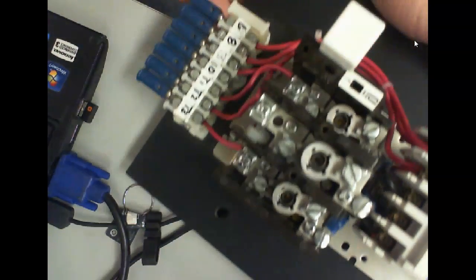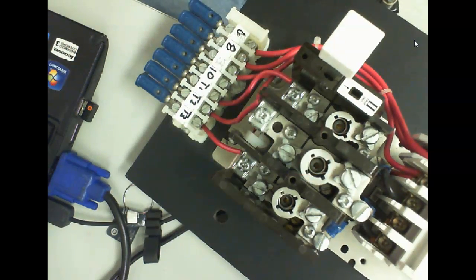This is a heater. We'll learn there's different types, but these actually use little heaters in here, heater coils. And of course, the more current you put in them, the hotter they get. And when they get up to a certain temperature, it literally melts solder. We'll show you how these things work. It's got solder in a tube, and as long as the solder is hard, the thing can't spin, it won't trip. But as soon as it gets hot enough over a certain period of time, the solder melts and it allows it to spin and kick out the overload.